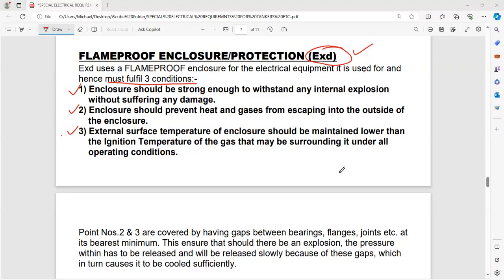And then you saw that even with that slight scratch that was there, that is why they say don't use emery paper or files or anything, because then you can create some damage to the flange, to the surface. And then you saw what happened. Just that slight scratch was more than enough, and you had that massive explosion. So that is EXD rated protection.